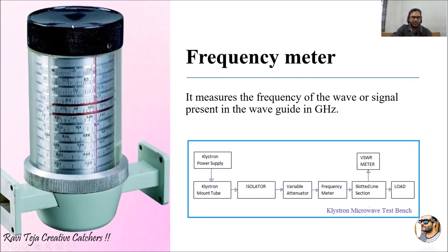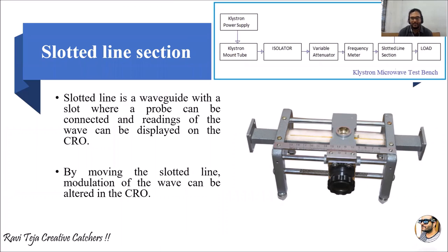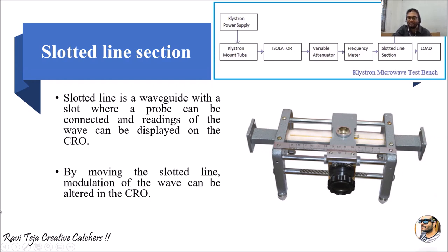Next comes the slotted line section, which takes the signal from the waveguide. It looks like a scale or vernier caliper attached to a waveguide, with a knob used for moving the slotted line to and fro. It is essentially a scale reading attached to a waveguide. A coupling probe or wire-type mechanism with a probe connection can be attached to the slotted line, and readings of the wave in the waveguide can be measured using a VSWR meter or CRO.